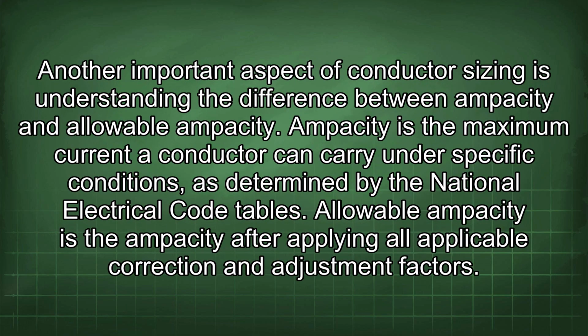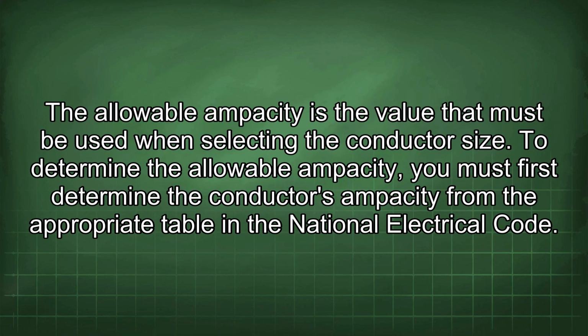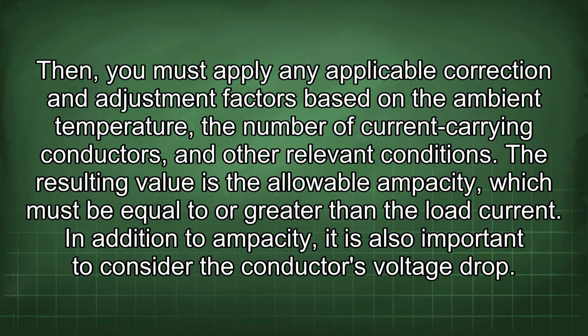Another important aspect of conductor sizing is understanding the difference between ampacity and allowable ampacity. Ampacity is the maximum current a conductor can carry under specific conditions, as determined by the National Electrical Code tables. Allowable ampacity is the ampacity after applying all applicable correction and adjustment factors. The allowable ampacity is the value that must be used when selecting the conductor size. To determine the allowable ampacity, you must first determine the conductor's ampacity from the appropriate table in the National Electrical Code. Then, you must apply any applicable correction and adjustment factors based on the ambient temperature, the number of current-carrying conductors, and other relevant conditions. The resulting value is the allowable ampacity, which must be equal to or greater than the load current.